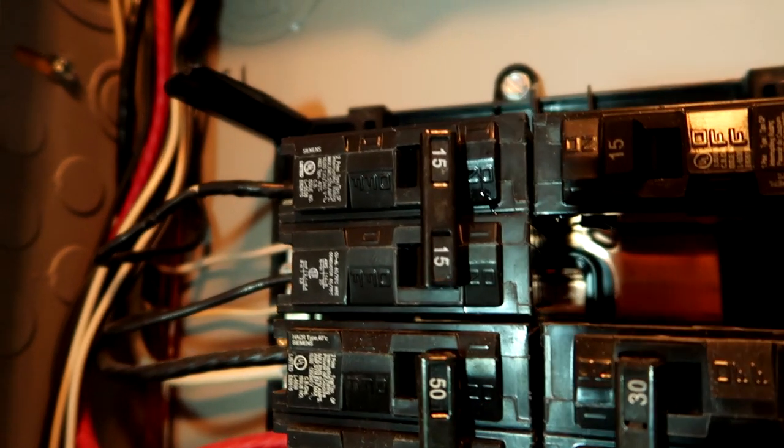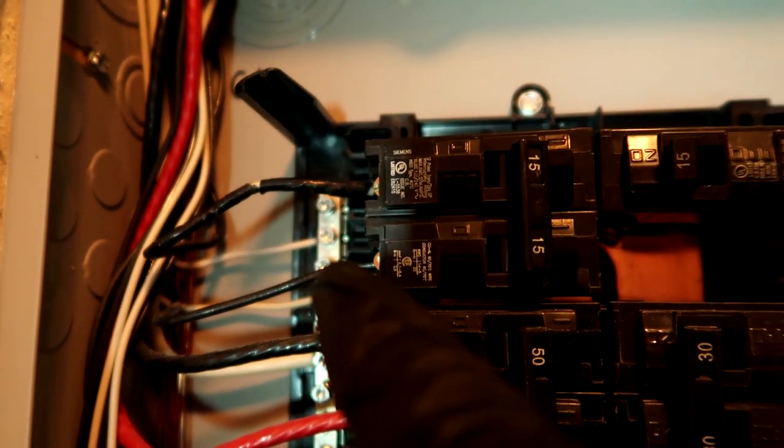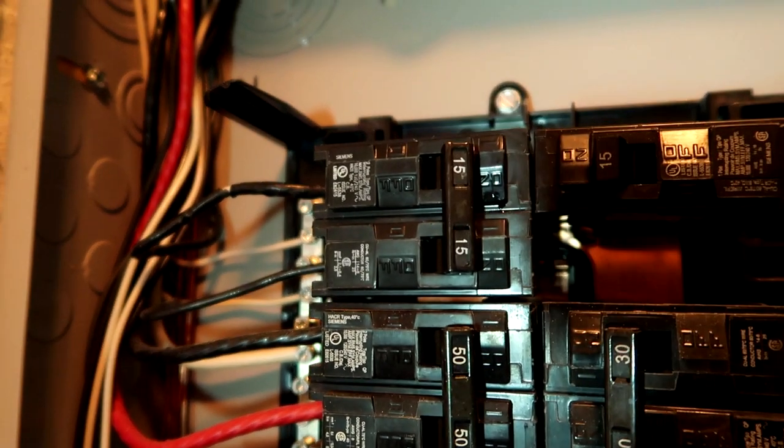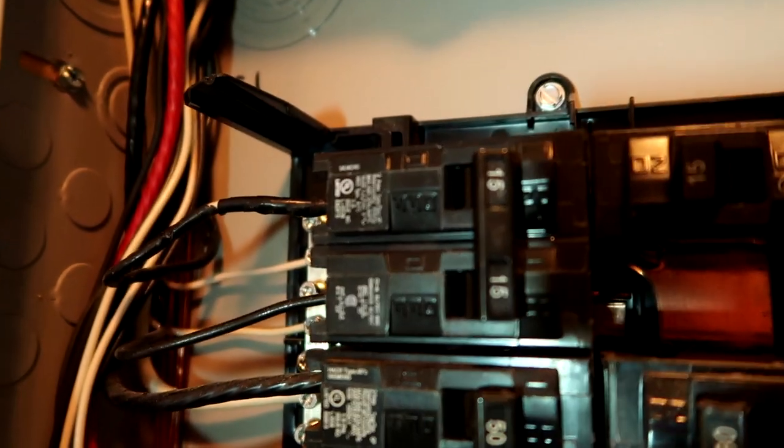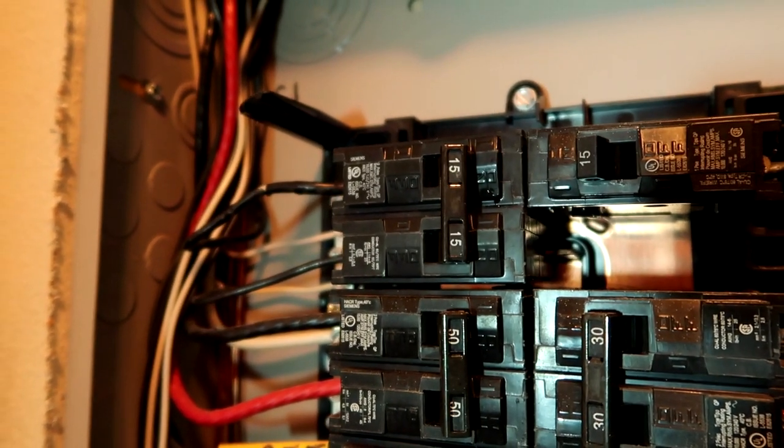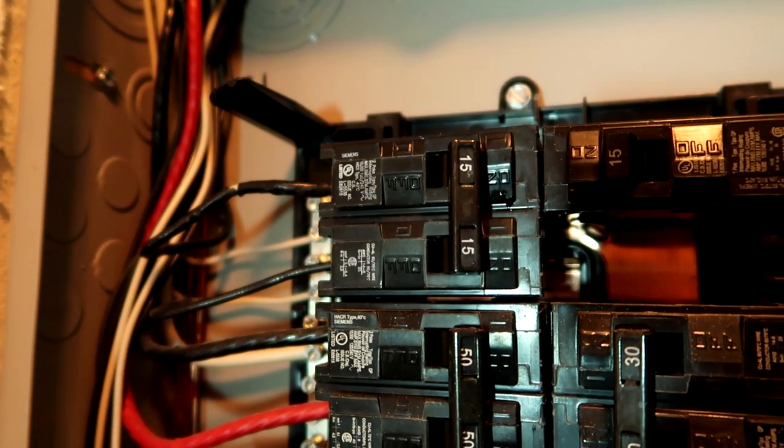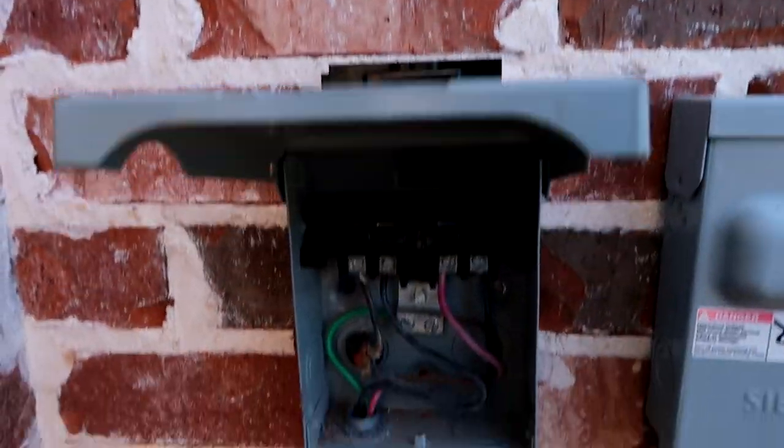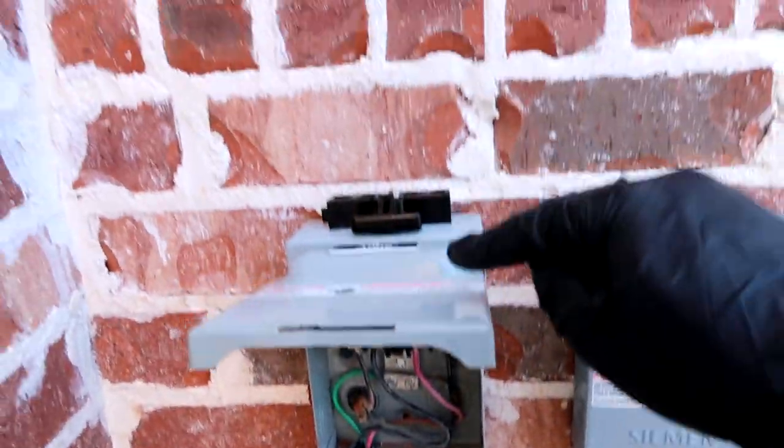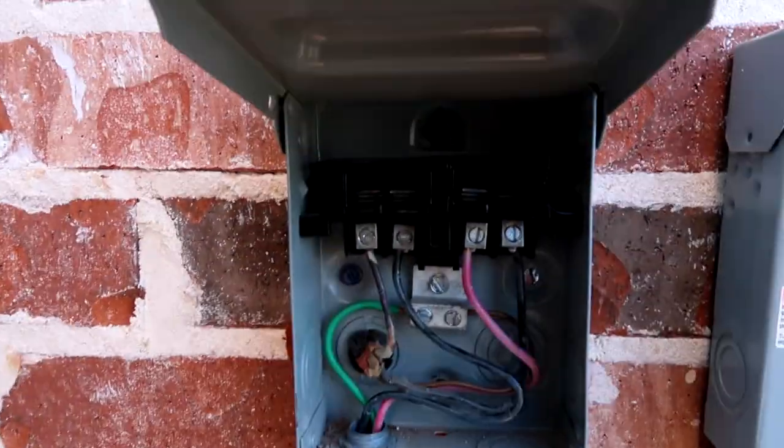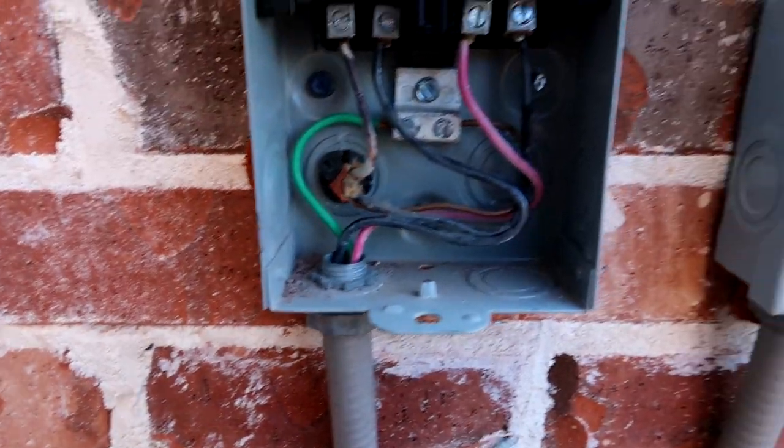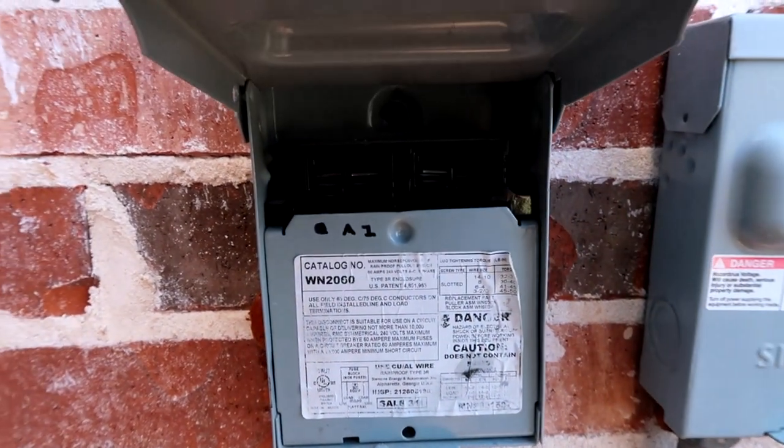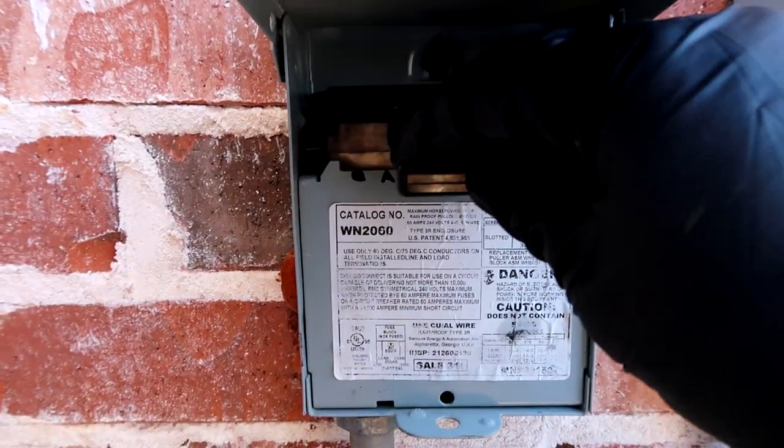All right guys, I put the same breaker back in. I just stripped it back to some fresh wire. It was beeping on continuity on both sides. I even ohmed it out, both sides were ohming at 5. So I put it back in, threw it back on, and as you can see it's staying on. Who knows? I'm going to go put the disconnect in and see if we have success. Yeah, so that breaker was tripping with the disconnect out, so the power wasn't even going to the condensing unit. It was in between here and the breaker box, that's why it was tripping. And I looked in here, everything looked good, nothing crazy or burned, no wires touching. So it was definitely between here and the breaker box, whatever it was. Maybe it just needed to take it out and cut it back to some fresh copper.